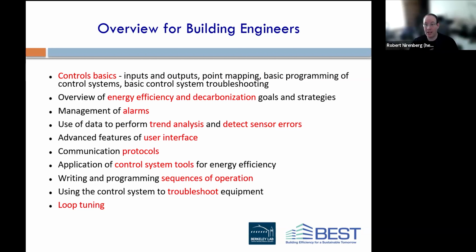Having worked as a building automation system technician and programmer for new construction, I can tell you there's not enough time on new construction or remodels for the control contractor to properly tune most of the loops in your building. Big systems, yes, but small systems, VAV boxes, and zone controls very infrequently get enough time to be tuned in for optimal operation. So that's something you can pick up yourself.